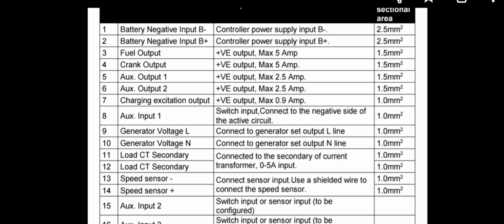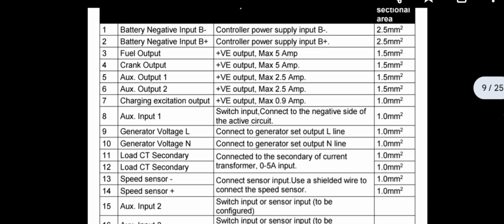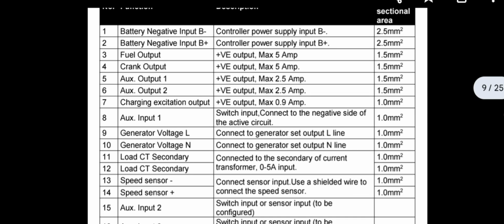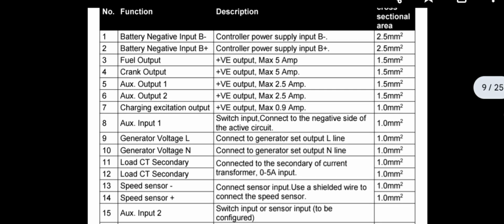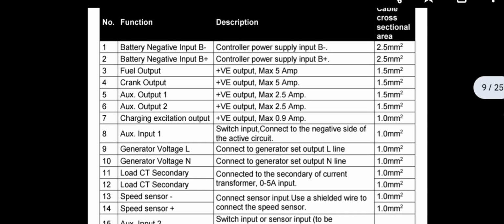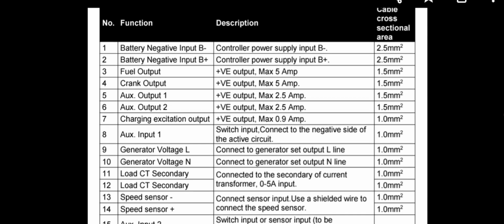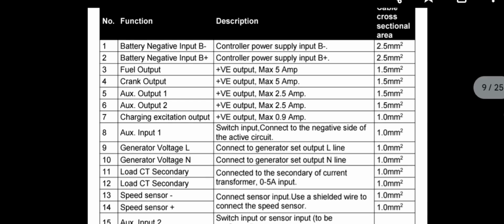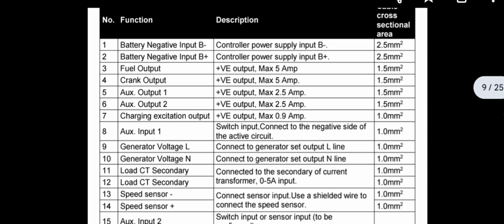Okay, pin number 1 in a controller backside is a battery negative input, and pin number 2 is a battery positive input. Okay, controller power supply input. Okay, this wire should be 2.5 mm square. Number 3 is a fuel output. This is the fuel output for the fuel turning on or fuel solenoid turning on. Okay, pin number 4 is a crank out. This is to operate the crank starter motor relay coil only.